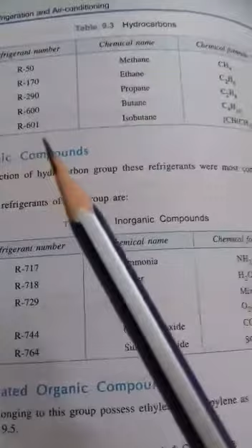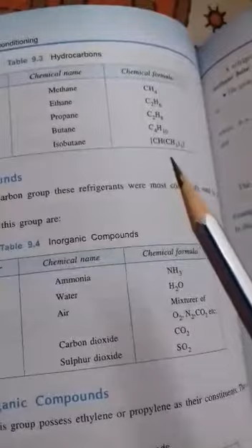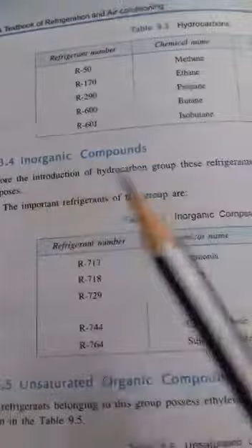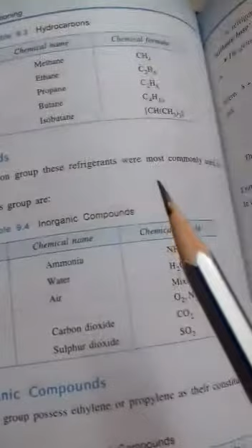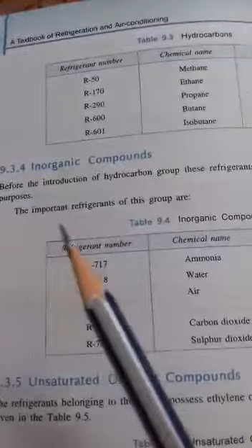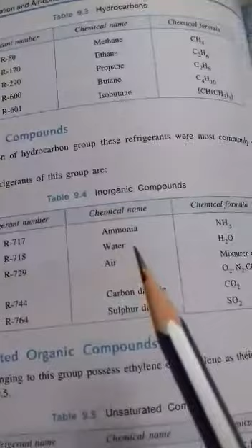Then inorganic compounds. Before the introduction of the hydrocarbon group, these refrigerants were most commonly used for the purpose. The important refrigerants of this group are R717, that is ammonia, R718, that is water, R729, that is air, R744, carbon dioxide, and R764, sulfur dioxide. These are the inorganic compounds used as refrigerants.